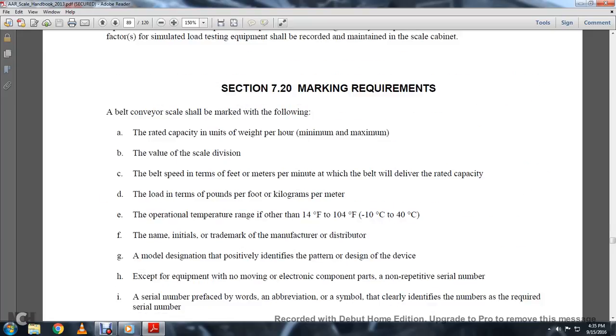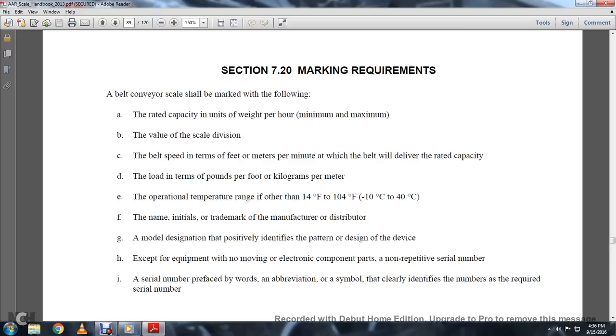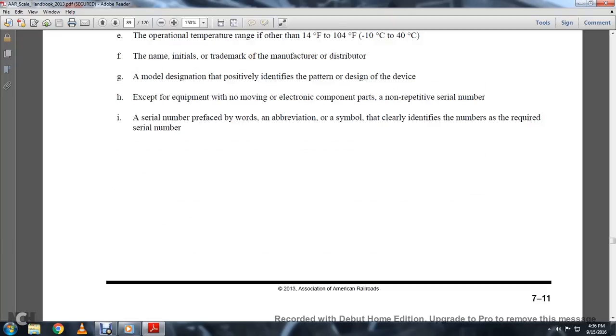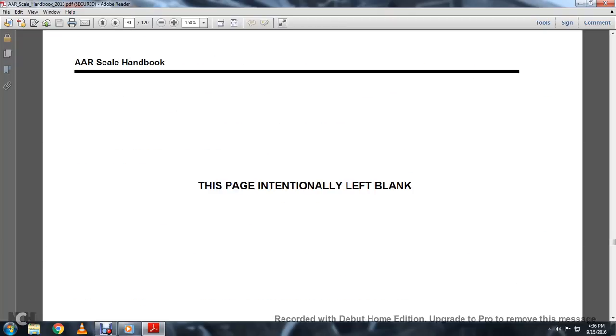Section 720, Marking Requirements. The belt conveyor scale shall be marked with the following: rated capacity units in weight per minute or per hour, max and minimum, max value of scale division, belt speed in feet and meters per minute, belt load capacity in pounds per foot and kilograms per meter, operational temperature range from 14 degrees to 104 degrees Fahrenheit, name, initials, trademark, manufacturer, distributor and model designation, pattern approval number, serial number, and any other required identifications. This page is intentionally left blank.